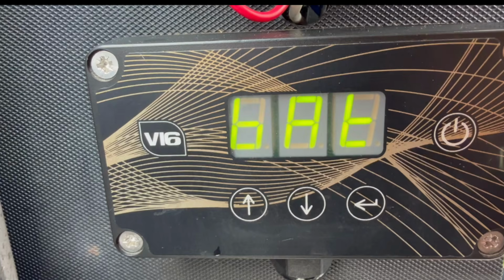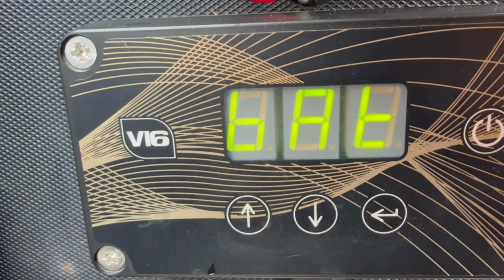Now, probably the next one I get calls for is BAT stop. Now, BAT, it's not Rise of Dracula, I'm sorry to say, it's not that dramatic, and it is just short for battery. STP, so you'll see BAT and stop, STP, battery stop. The controllers have a battery protection mechanism. They also have a voltmeter. So the voltmeter is reading the voltage of the battery across the two terminals. However, take into account that then that's travelling down 2 meters of cable. So you might find your battery's got 12 volts and the controller might see 11.9. That difference is because of the run of cable.